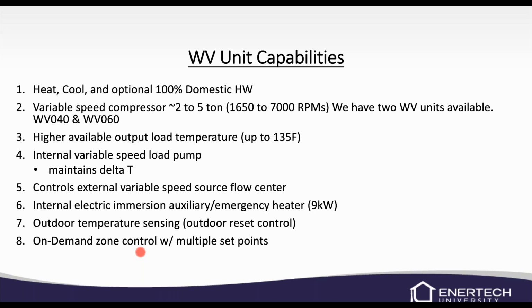We have higher output load temperatures, so we can get up to about 135 degrees. That works well when we're doing our domestic hot water. We've got plenty of range there for the domestic hot water, as well as doing some forced air heating and cooling with hydronic air coils. There's an internal variable speed load pump, and basically it will maintain your delta T. And then the unit will control, based off of a control wiring, the external variable speed flow center.